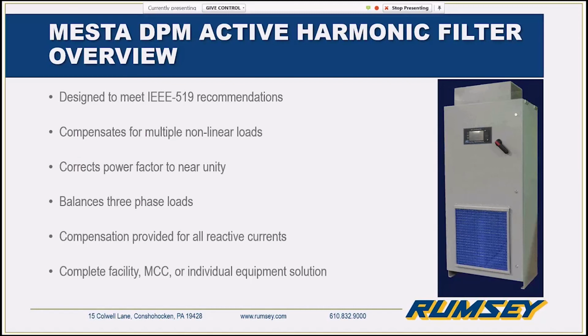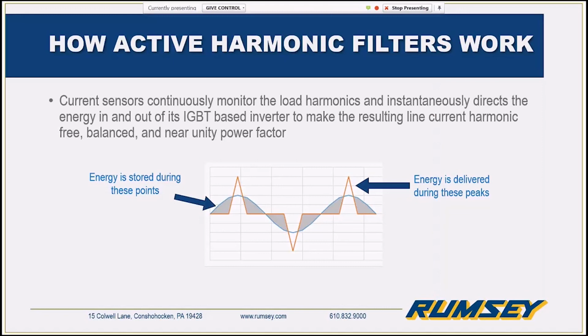And again, as we had just talked about, being a complete solution from a facility start all the way down to the load. So how do we work? Active filters use a set of current sensors on the line, and we're continuously monitoring the load, trying to see exactly what current those loads are trying to source for. And during the waveform, and this is a look at a simplified single phase version of it here, we actually take in energy, converting AC to DC, storing in our DC capacitors during parts of the waveform that are correct, and then we deliver all of this high frequency current downstream for the VFD loads so that the utility or the generator doesn't have to provide it.